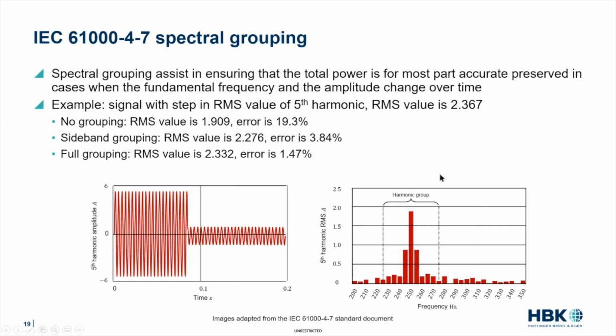Now, if I calculate the fifth harmonic without grouping, so in the flavor no grouping, I end up with an RMS value of 1.909, which is a deviation from the true value of 19.3%. So that is quite a big error. If I use sideband grouping, I do slightly better. Then I have an error of 3.84%. And when I use full grouping, I'm doing even better, and then I have an error of 1.47%.